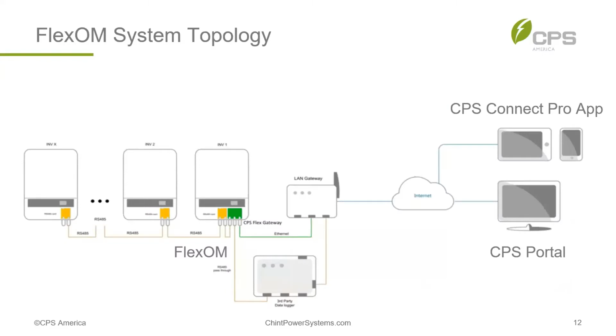This slide shows the typical Flex system topology as represented by the single line diagram, with the Flex card mounted inside the inverter wire box. Up to 32 inverters may be daisy chained together on the Modbus RS-485 network, and the outbound Ethernet port is connected to either a wired or wireless LAN gateway router, accessible by the CPS portal or by smartphone or tablet with the Connect Pro app.